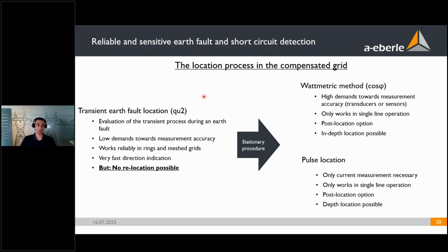It has really low demands towards measurement accuracy and works reliably no matter your grid structure. So in rings and mesh grids, and of course also in single line operation. And it has a very fast direction indication. But the main disadvantage of the transient location is that you do not have the possibility of relocation. So when you perform switching operations to further single out the faulty segments, then your transient method will not help you.